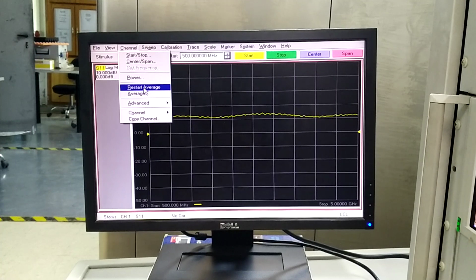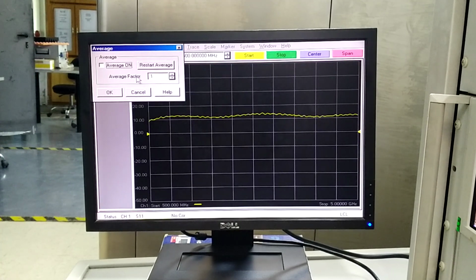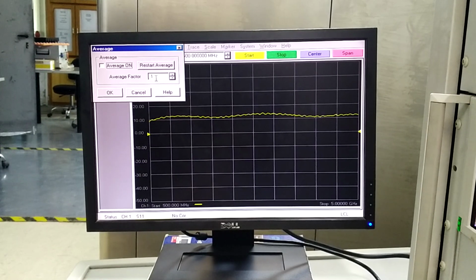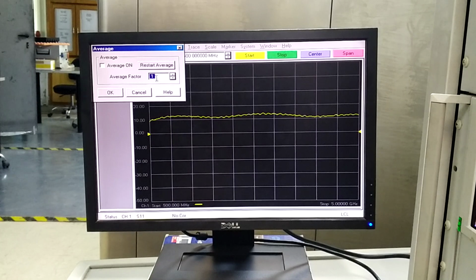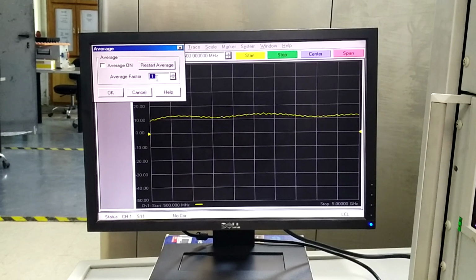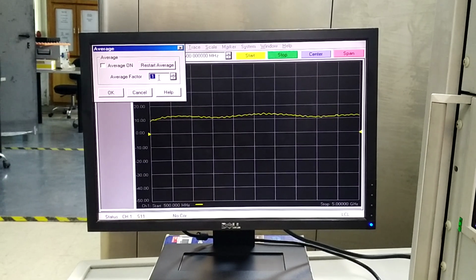Now there are also other options like restart average, or the average option. For example, if I click the average option, here the average factor is 1. This means that all the frequency points I measure only once and display on the screen. If you would like to do very precise measurements and you think your measurements change with time, you put an average factor. If I put, let's say, 10 here, it will perform the sweep 10 times, each frequency point will be measured 10 times, and the average value of these 10 measurements will be displayed for each particular frequency point. In our case, we just put an average factor of 1, so in a single sweep it will display the values. So I just press OK.